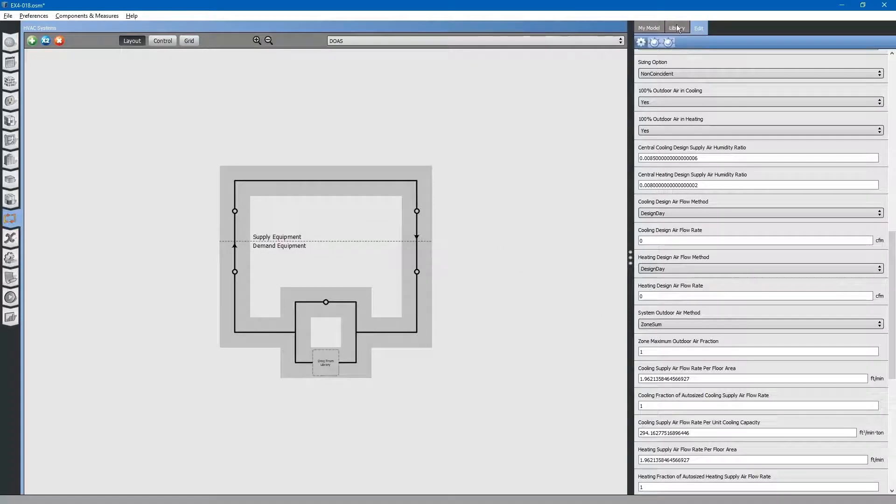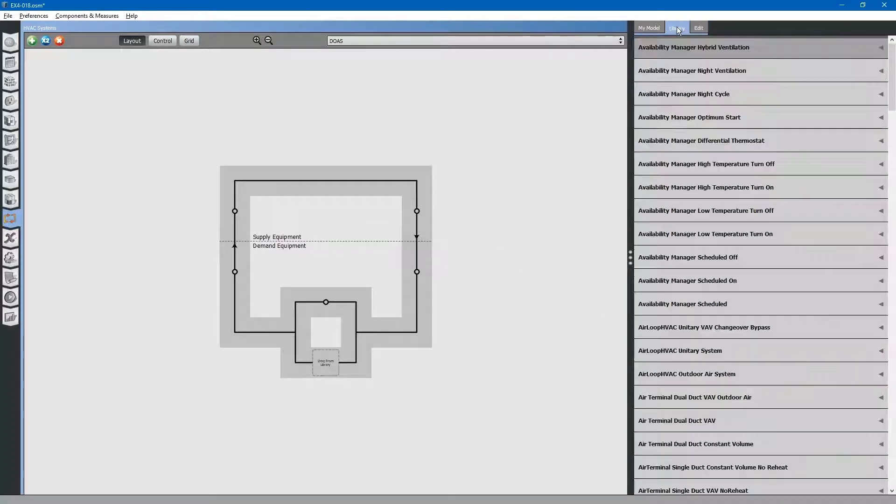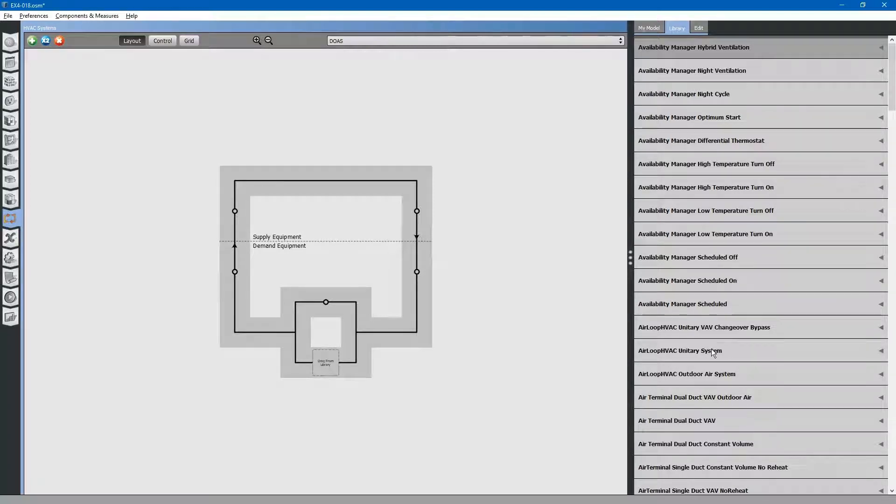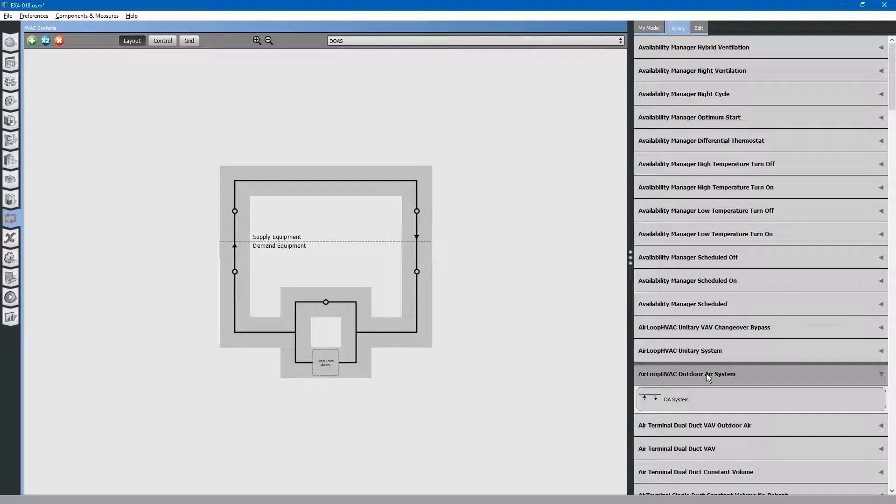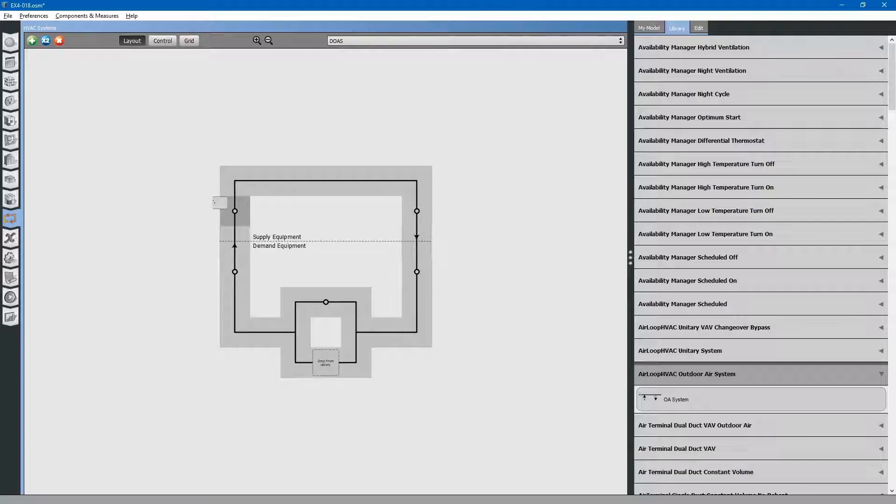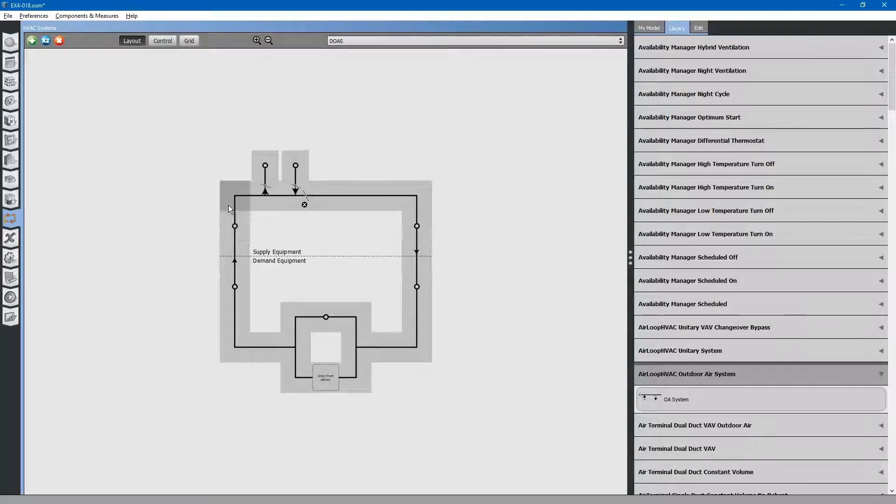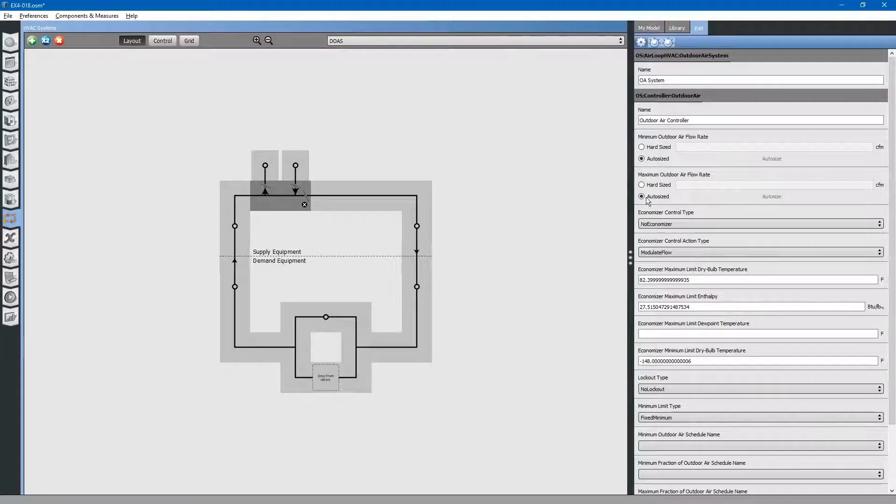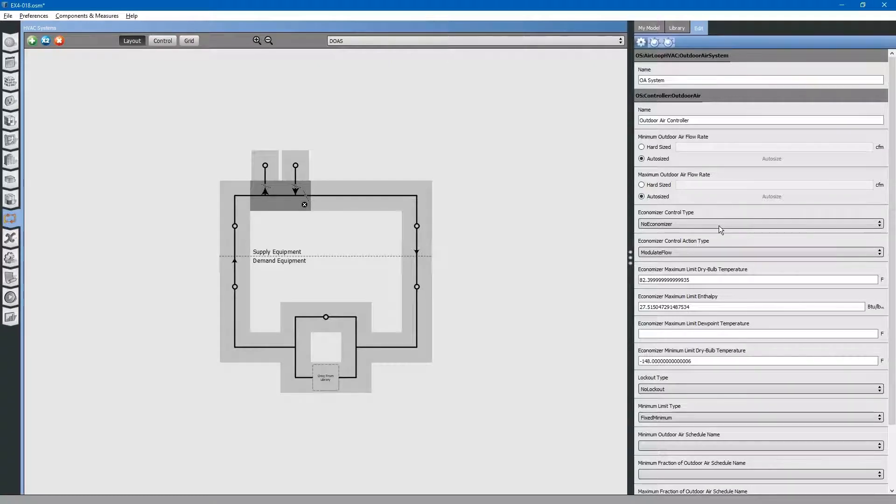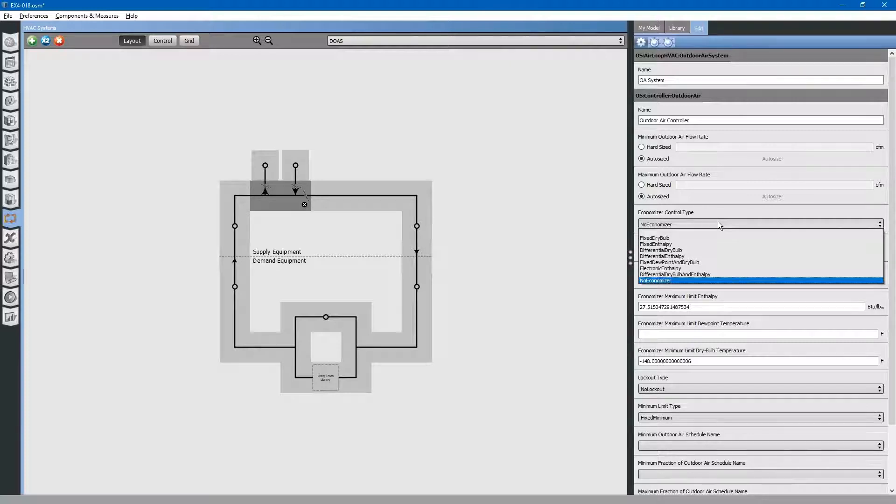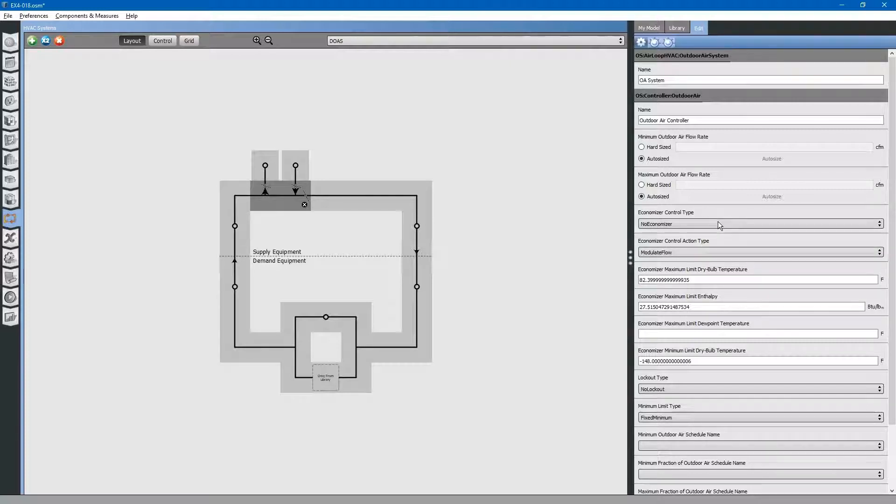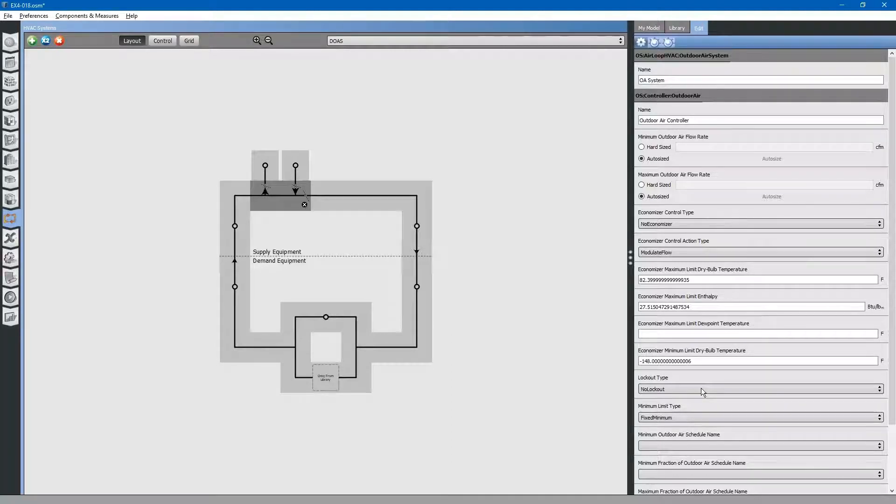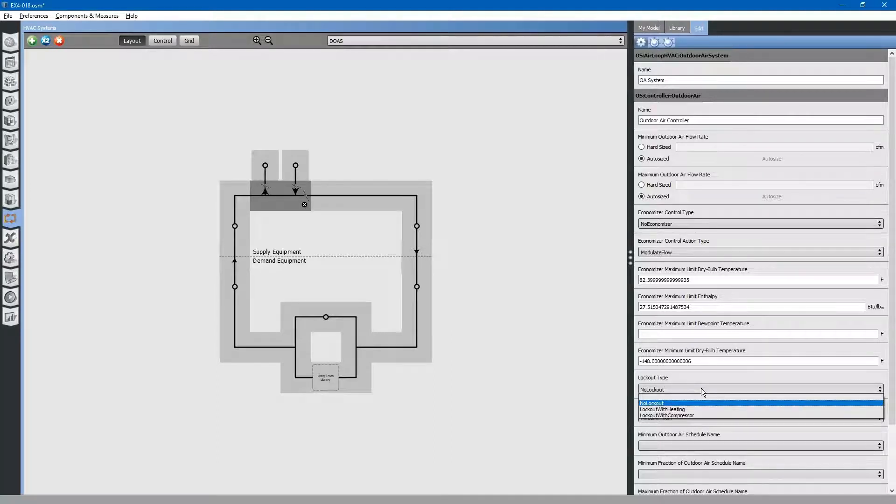Next, we will go to the library tab. Search for air loop HVAC outdoor air system. Drag and drop it to one of the supply side nodes. Select it to edit the properties. We will leave it auto sized. There is no economizer, so we will leave this checked to no economizer. There is also no lockout, so we will leave this checked for no lockout.